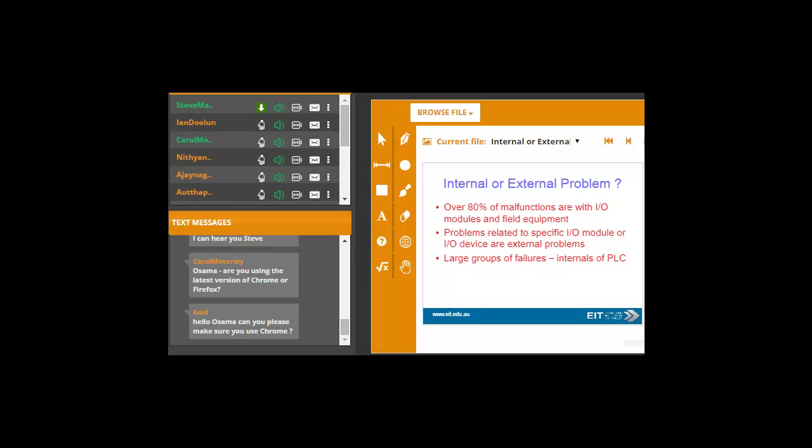External are your field contacts, digital inputs, and internal are obviously the PLC itself. PLCs are very robust. They are pretty idiot-proof. They work really well. But external, you don't know what could be the problem. It could be a field input, it could be the cabling, it could be interference. So 80% of malfunctions estimated are I/O modules external to the PLC. PLC itself is pretty well bulletproof. But the external environment is not bulletproof because all sorts of things could happen. So 80% of your problems will occur externally.